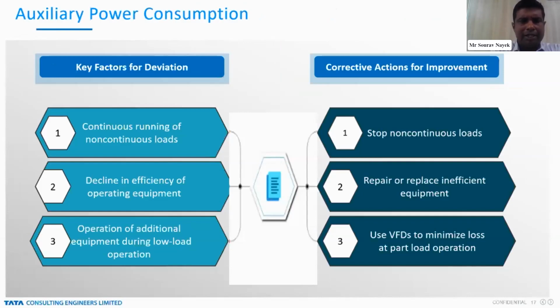The auxiliary power is another aspect which affects the heat rate. One is the continuous running of non-continuous loads, decline in efficiency of operating equipment, and operation of additional equipment during low load operation. So these are the key factors for deviation. What are the corrective actions? During operation, we should stop the non-continuous loads, and replace or repair the inefficient equipment. When we are running the plant at minimum load, we should always use the VFD, or operate with a single stream operation, so that we can minimize the loss at part load. Auxiliary power also has a large impact on the heat rate, and with these corrective actions we can improve the heat rate of the cycle.